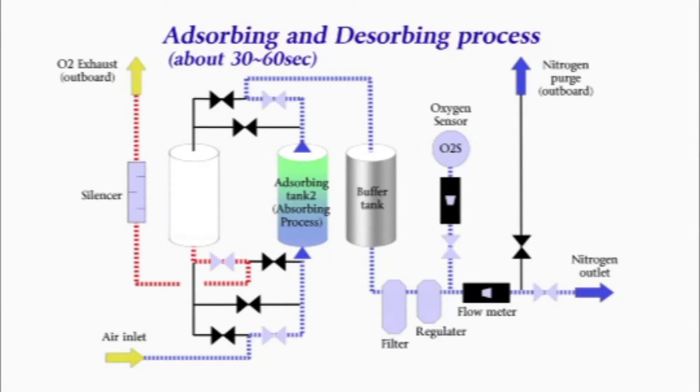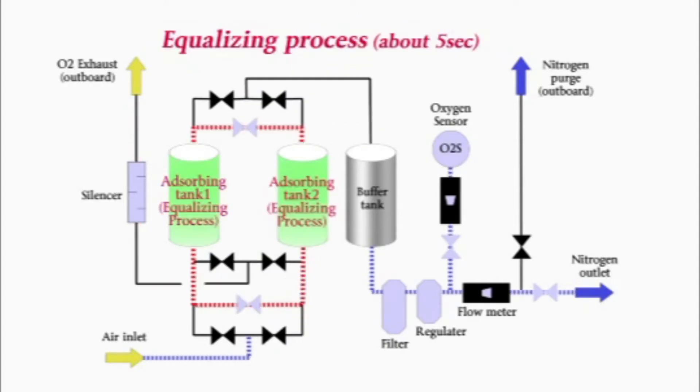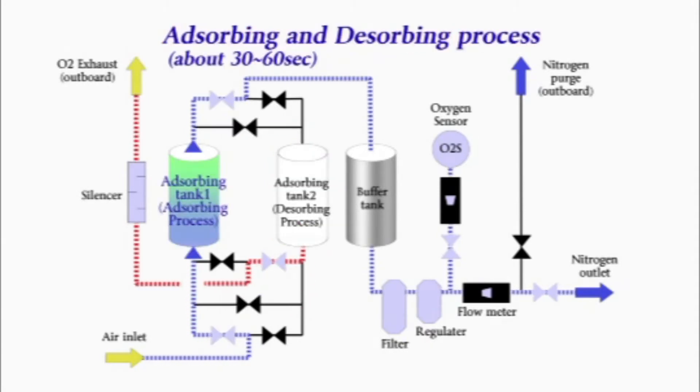After this, the adsorbents are recovered by purging the pressure inside at once. This is called the desorbing process. By repeating the adsorbing and desorbing processes alternately between one tank and another, it is possible to continuously produce nitrogen gas.